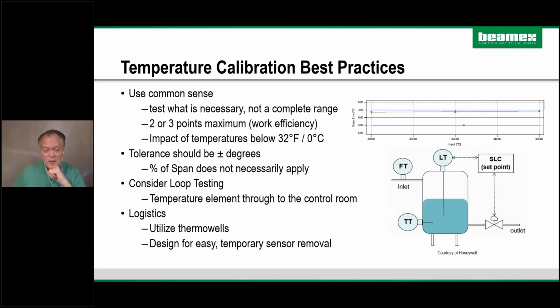And then finally, when people design a plant, many times they overlook utilizing techniques that make calibration easier. Many times in furnaces, this is a tank, but in a furnace, you might have a thermowell that's in parallel to the temperature sensor, and you can make a spot check. You want to be in close proximity to the field measurement probe, and you can do that if you put a thermowell in there. In this drawing, if you see the temperature transmitter on the side, if this is 10 feet off the ground, if these legs are really up in the air, how do you get up there with your dry block? Do you have enough cabling to pull this down to the floor?